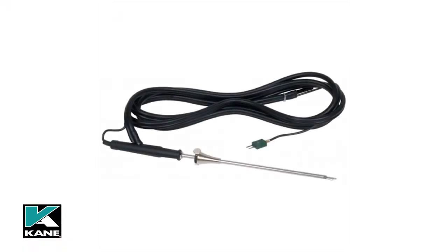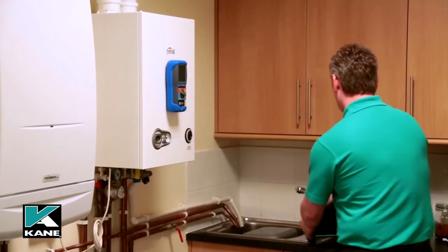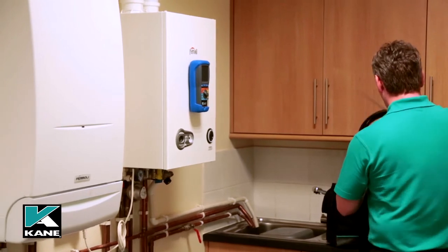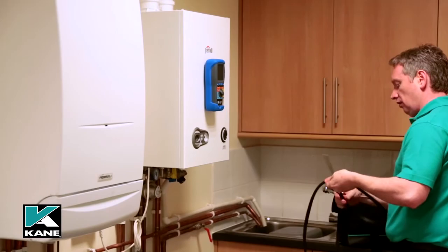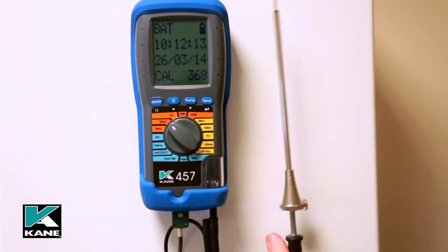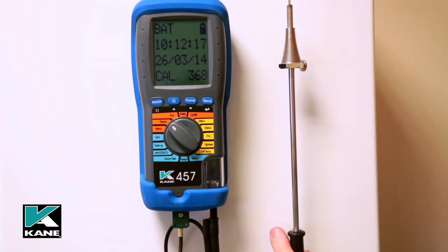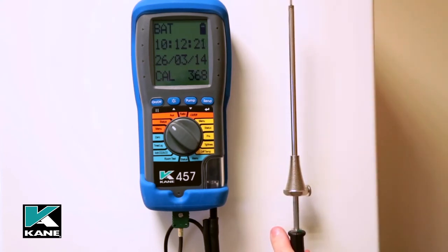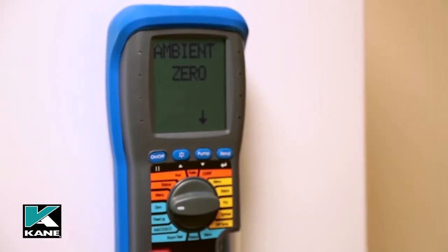The flue probe is an important part of the analyzer and is manufactured to a high specification. The 3m hose and stainless steel probe incorporates a thermocouple temperature probe providing accurate flue gas temperature measurement. The adjustable depth stop cone ensures accurate positioning into the flue. There is also an inlet for the CO2 zero calibration capsule, which will be covered in more detail later.